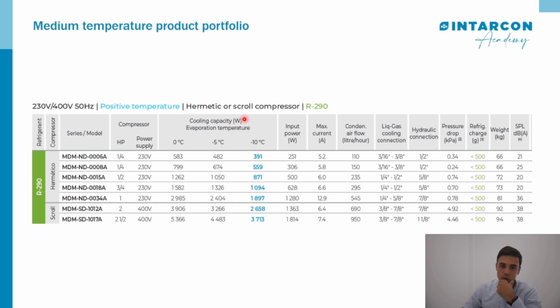If we think about the cooling capacity range for an evaporating temperature of -10 degrees, we will have a cooling capacity range between 400 watts and 3.7 kilowatts. It's important to keep an eye on this column, this pillar, that will be the condenser airflow. Sorry, that will be the part with the pressure drop that we will have in the plate. It's also important to know the refrigerant charge is lower than 500 grams of propane, so it's suitable to install in most types of installation.